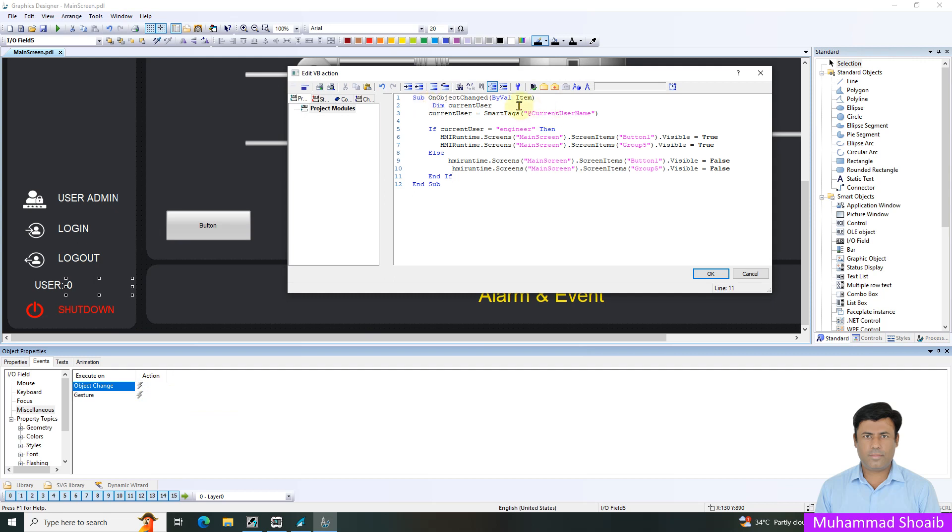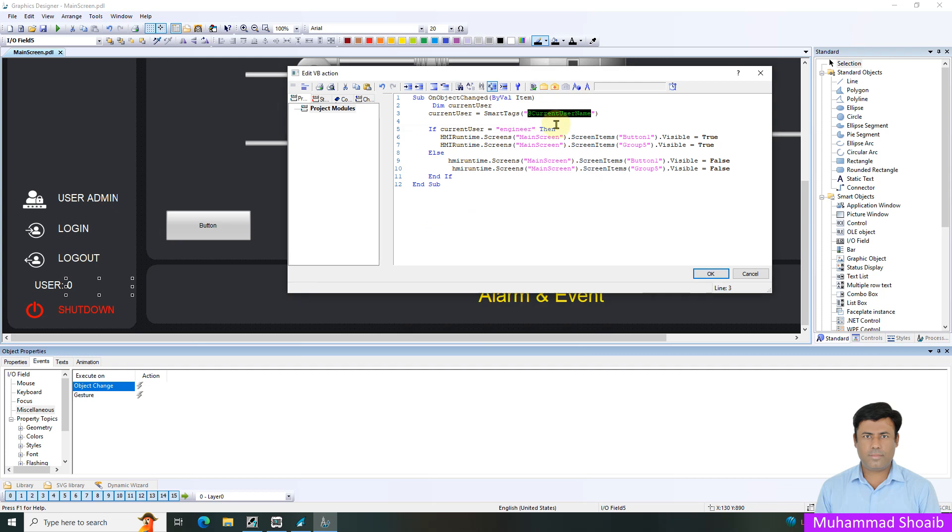How it will work: we will create one current user variable and then I will import the current username internal object value inside this variable. From where you can take it: click here and come to internal tag. Here you can find current username. Just press OK, then it will import this whole name. This mod tag will bring, it will move our tag current value inside the current user variable.